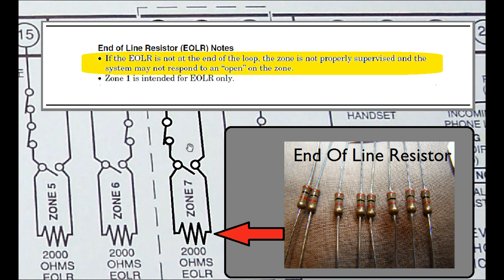If the end of line resistor is not at the end of the loop, the zone is not properly supervised, and the system may not respond to an open on the zone. So make sure this resistor is the last hookup in your loop.